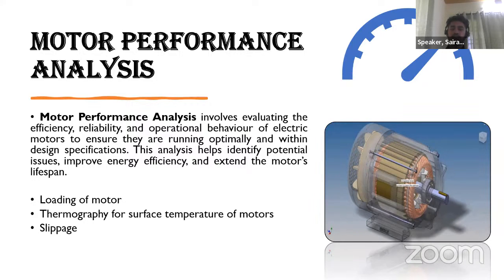Then for slippage, we will be checking the efficiency of the transmission: how effectively the mechanical energy generated by the motor is transferred to the utilization, like to the process. In the loading of motor, we will be getting an idea whether the motor is getting underutilized or overloaded. Based on that, we can give suggestions for the improvement of the energy efficiency. Then the thermography will most probably reveal the higher winding temperatures. Then slippage will be revealing the transmission loss.